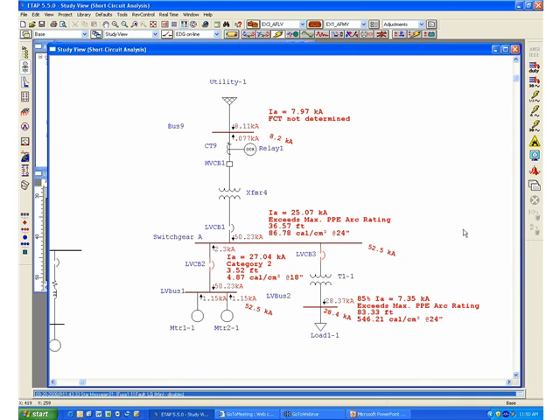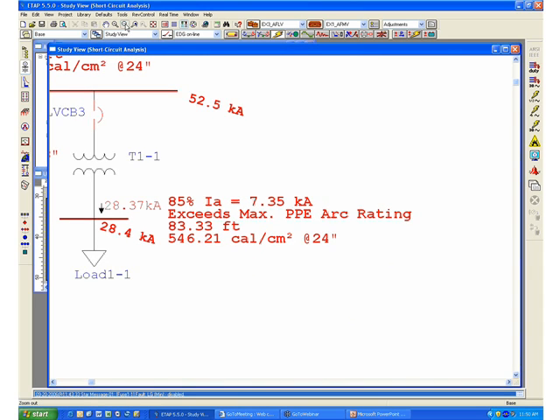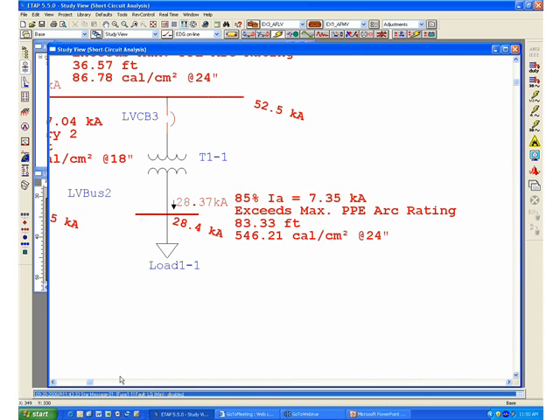One of them indicates that the program automatically determined or applied the arc-current variation at 85% of the original arc-current value. We can see that the amount of incident energy released is very high, and most likely this is caused by the long full clearing time response of the upstream protected device in this system.